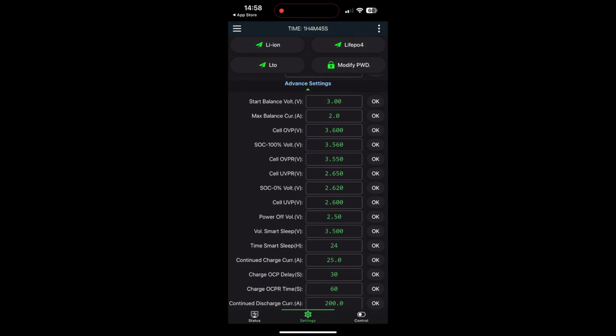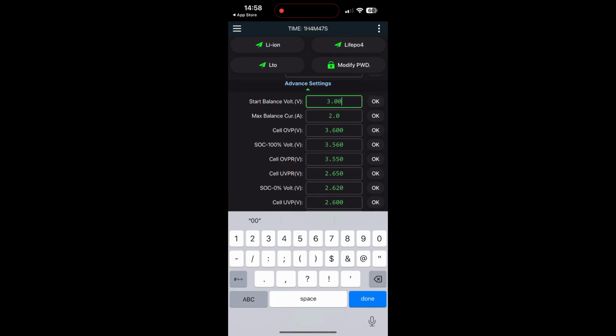So the advanced settings, start balance volt. What voltage do we want before the active balancer within the BMS starts to balance? Now, there's some people out there that say they want to leave it until later in the charge profile to do it, say 3.4. I personally don't agree with that. The reason being is that between 3.4 and 3.65, the voltage in a cell can increase dramatically at that point in the charge profile.